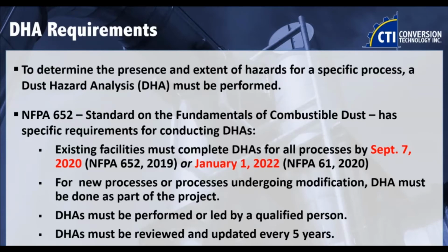So those of you that deal in feed and food and agricultural products, January 1st, 2022 is your deadline. So this is for all current processes and equipment. For new processes or processes undergoing modification, pretty extensive maintenance or replacement or refurbishment, the DHA needs to be done before startup. So I would include that in your timeline for that project, for that capital, for that equipment installation. A DHA must be performed by a qualified person.